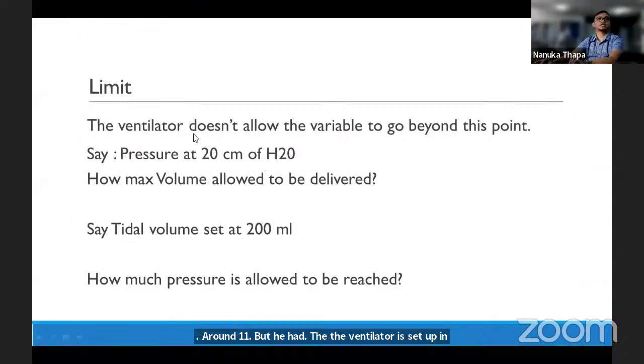What are the other limits that the ventilator will not allow this variable to go beyond? Like I said before, if we set the ventilator pressure at 20 centimeter of water, above this pressure the ventilator will not give, because it might cause injury to the patient, such as volume trauma or pressure trauma. How much maximum volume is allowed to be delivered? If we set the tidal volume to 200 ml every breath, the ventilator will not deliver beyond this. How much pressure is allowed to be reached? This is set by the peak inspiratory pressure.